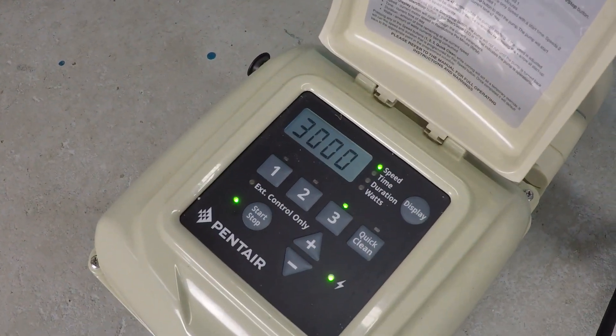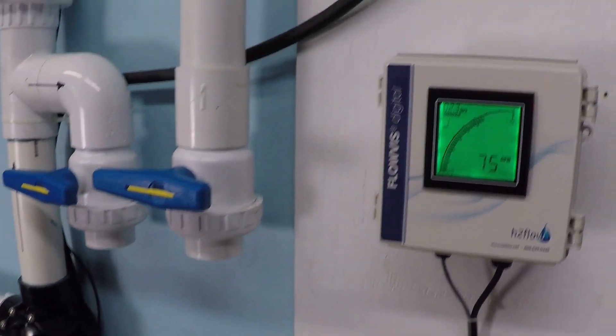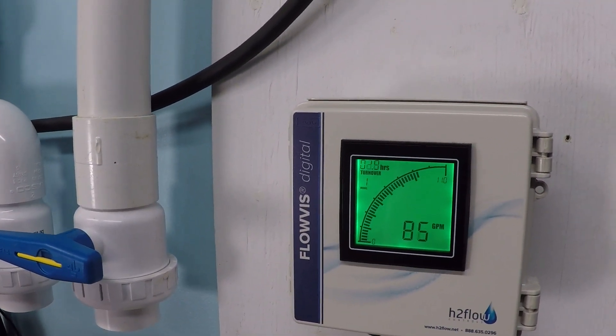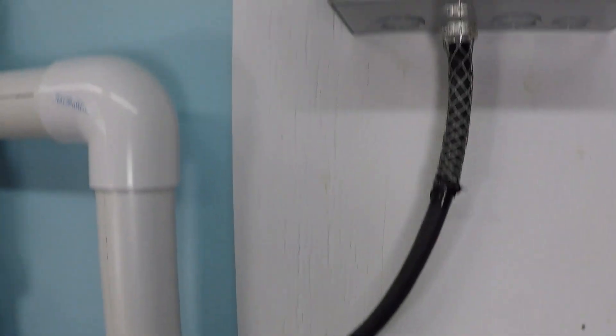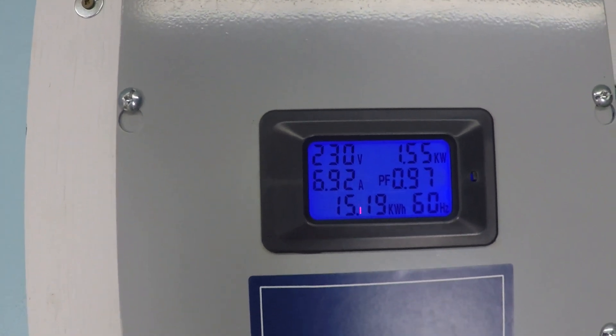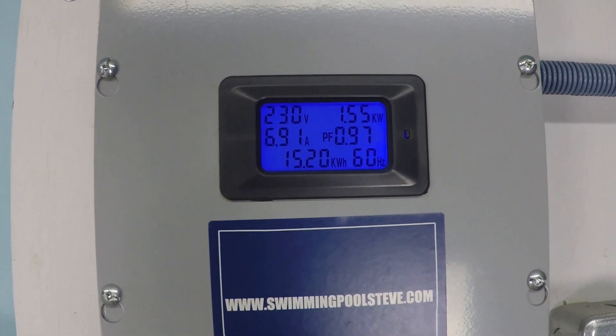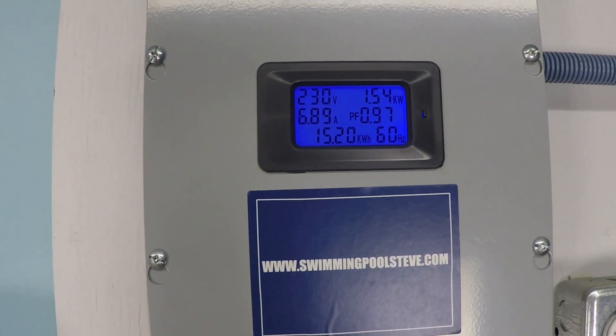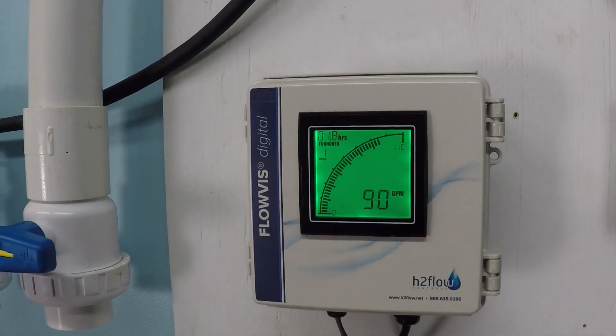First, let's run at 3,000 rpm. The flow meter reads 90 gallons per minute, and the power consumption in the top right corner shows 1,550 watts — about 1.55 kilowatts. That's 90 gallons per minute at 3,000 rpm.